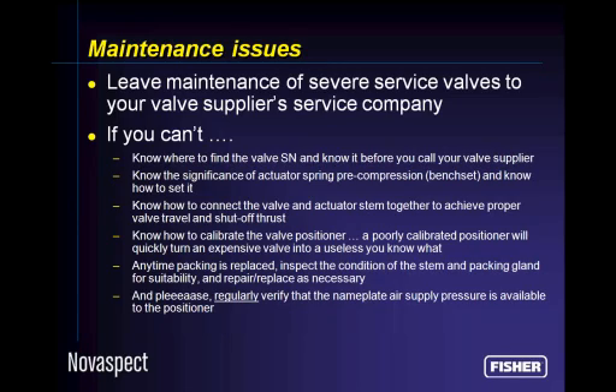The simple process of connecting the actuator stem to the valve stem is often done improperly. Read the instruction manuals. Make sure you know how to do that. It's the only way to ensure that you get the appropriate shut-off thrust of the plug against the seat. Know how to calibrate the valve positioner. A poorly calibrated positioner will quickly turn your most expensive severe service control valves into useless you-know-whats. Anytime packing is replaced, make sure you inspect the condition of the stem and the packing bore. It does no good to replace packing in a valve if either one of those is in bad shape, because it's just going to start leaking right away again, and you've wasted your time opening up the valve and replacing the packing.